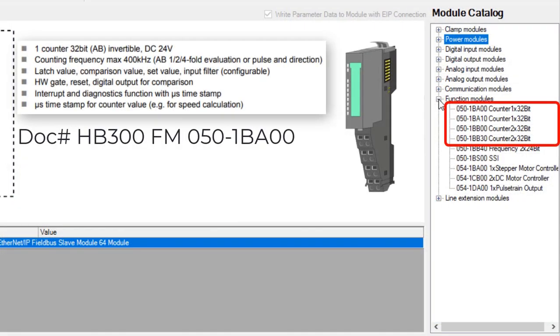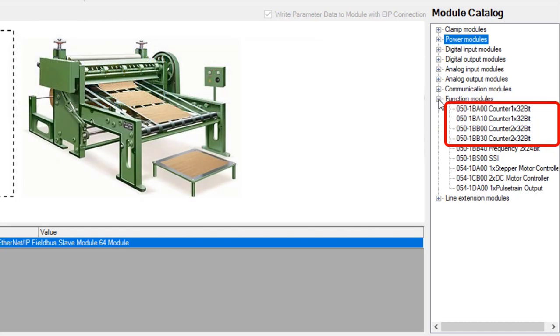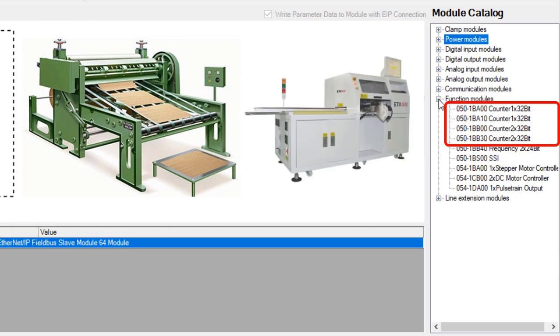The counter function slice provides a hardware counter solution that allows high-speed latched value capture, value comparison, configurable input filters, and A-B encoder input. Some applications that may benefit from this slice are rotary knives and high-speed placers.